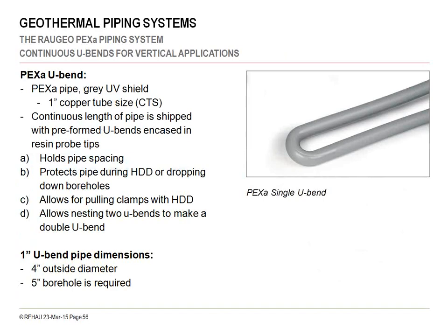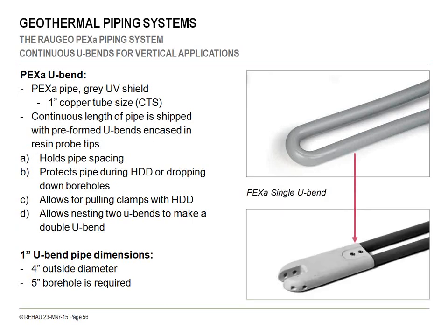Here's an illustration on the 1-inch piping material, and here's the U-bend that's formed in the factory setting with a bending table with radius fixtures that has some heat. We've got a process for controlling the wall thickness in the radius area of the U-bend so that the wall does not get too thin. After forming that U-bend, there is a casting operation of this probe tip, this white probe tip. It's a glass polyester resin.